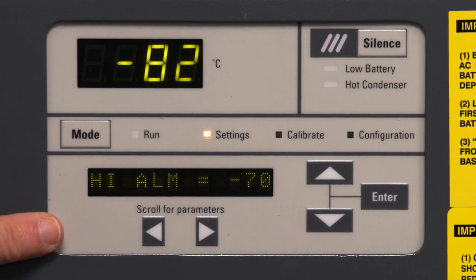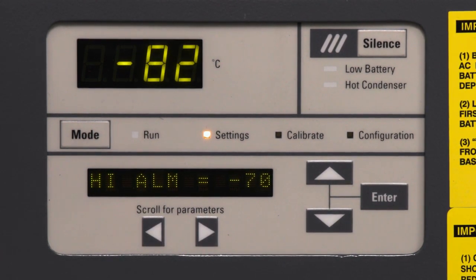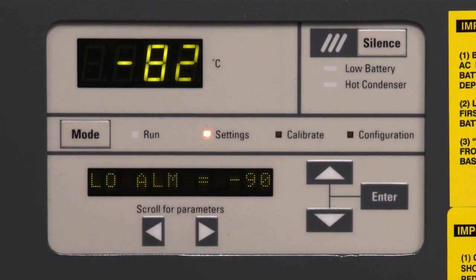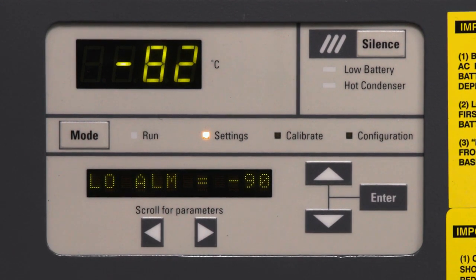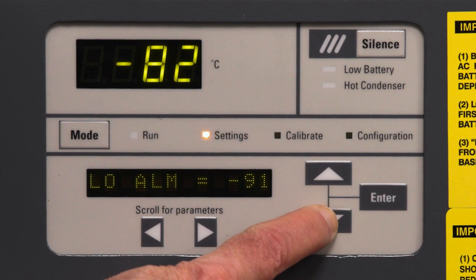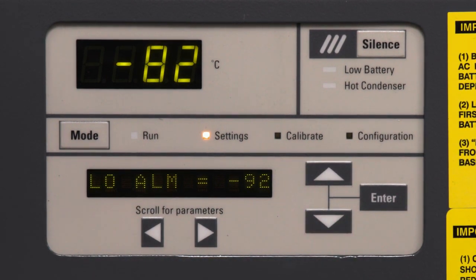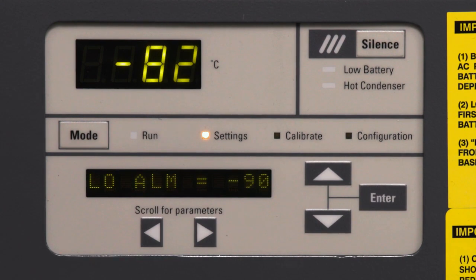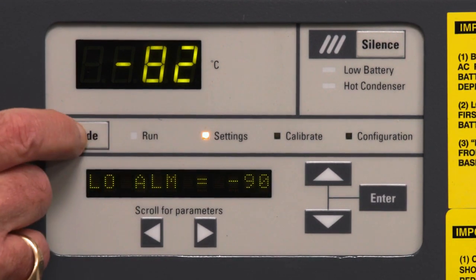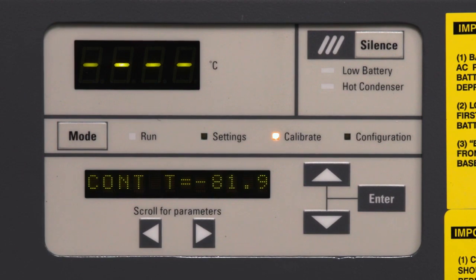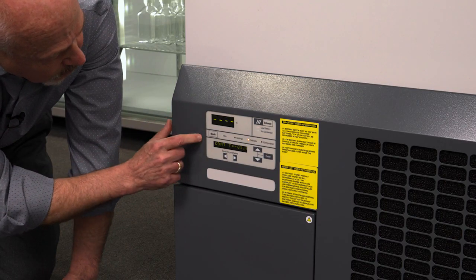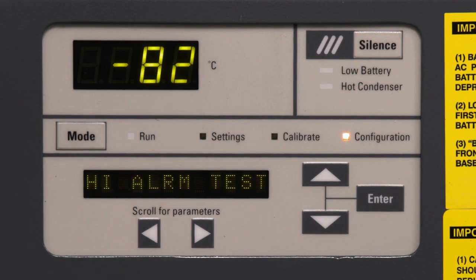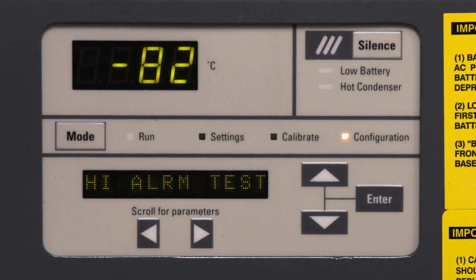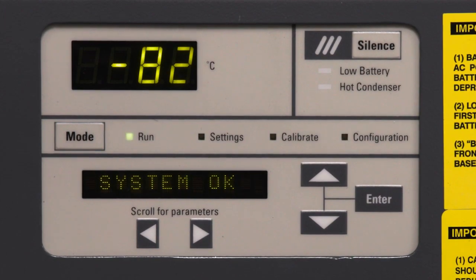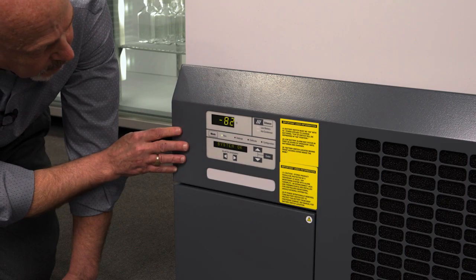We also have high alarm, so it will alarm at -70 degrees as a factory set point, or low alarm at -90 degrees. If I want to change any of those parameters, it's just a matter of toggling and then hitting enter to be able to change that parameter. I'll put it back to the standard. We also then can change over to calibrate, that should I want to make any calibration adjustments, I can do that in this mode. And then configuration, or specific configurations, I can do that in this mode as well. But normally we would be in the run mode, and this is what you would see on the display.